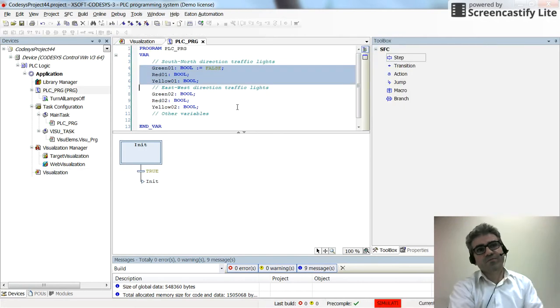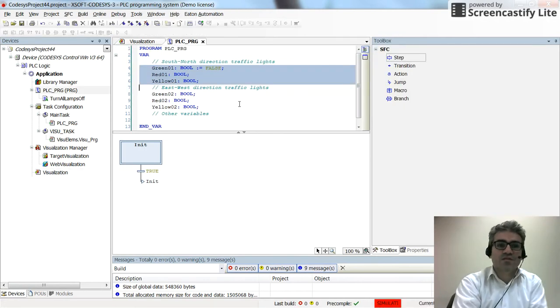Now, in the main program, I'm going to create a code using the SFC programming language in order to control the turning on and off of the pilot lamps in each direction. And for that, I will have this policy that the green light will be turned on for 5 seconds, then the yellow light will be turned on for 3 seconds, and then the red light will be turned on for 8 seconds in each direction. Okay?